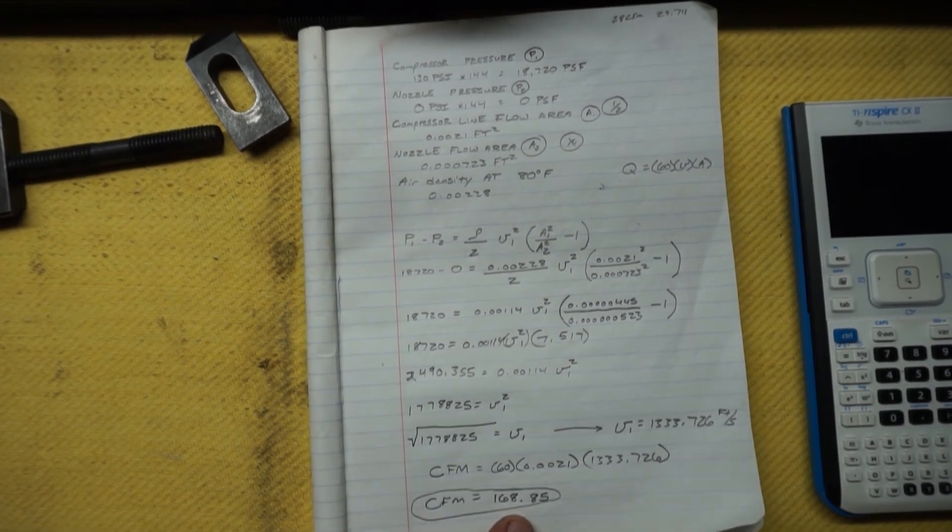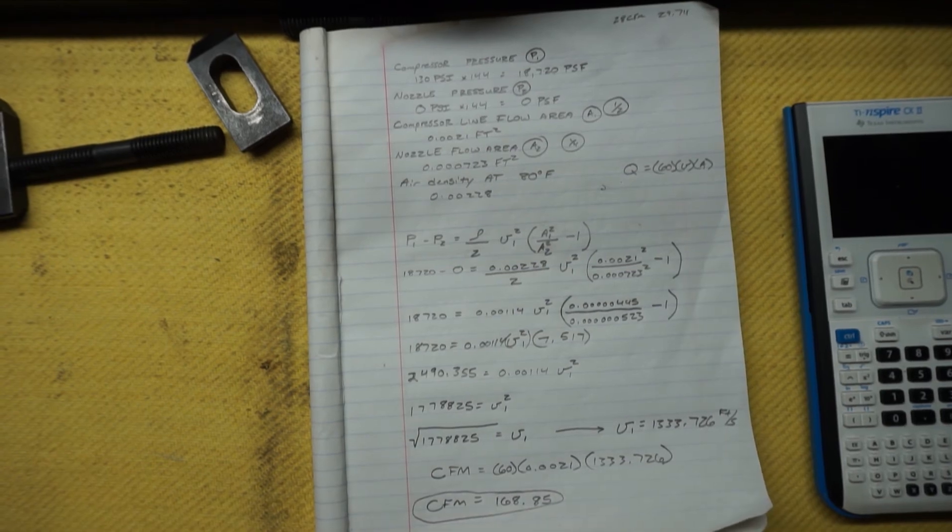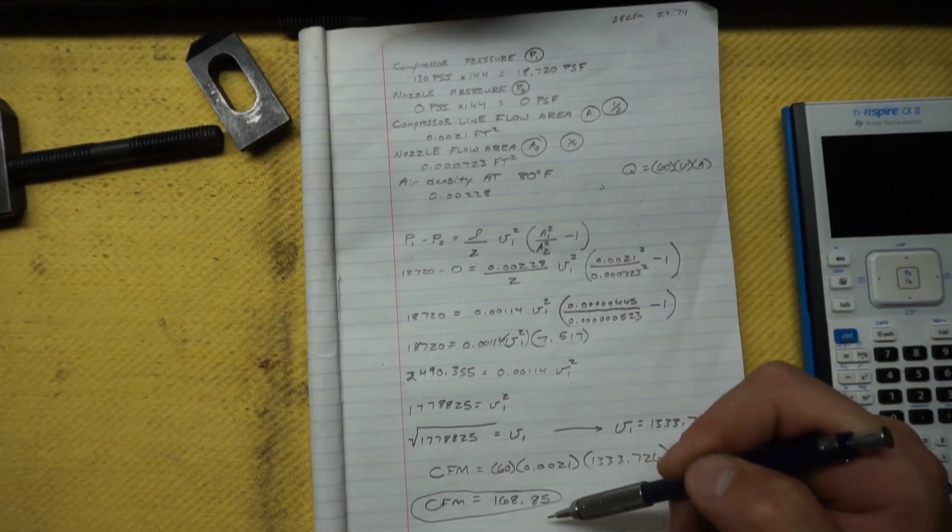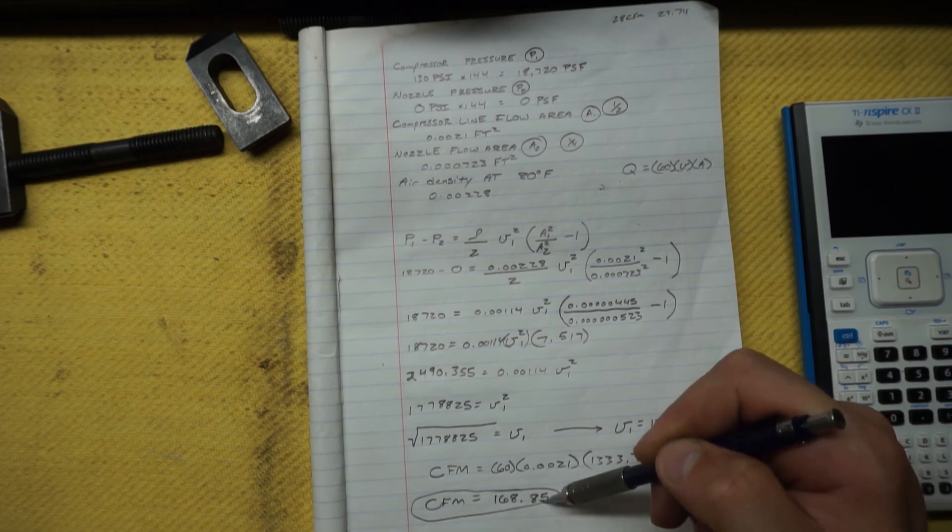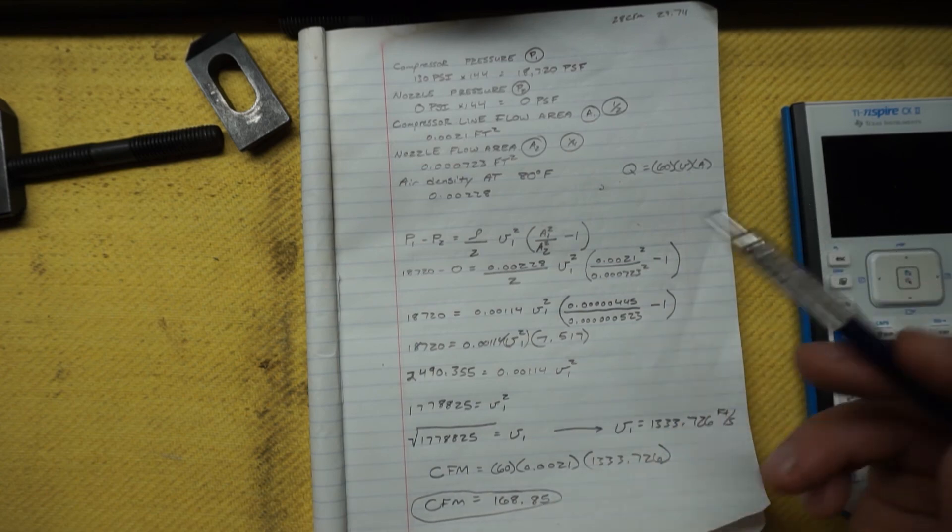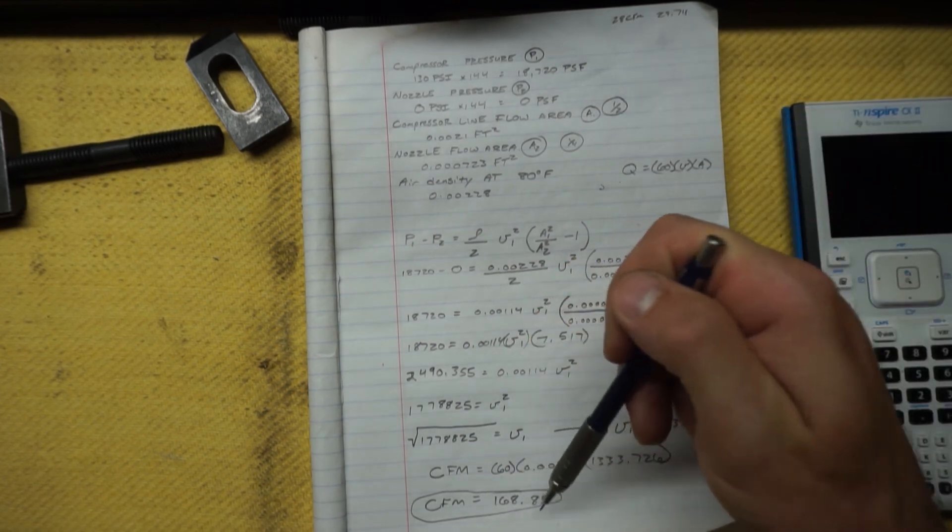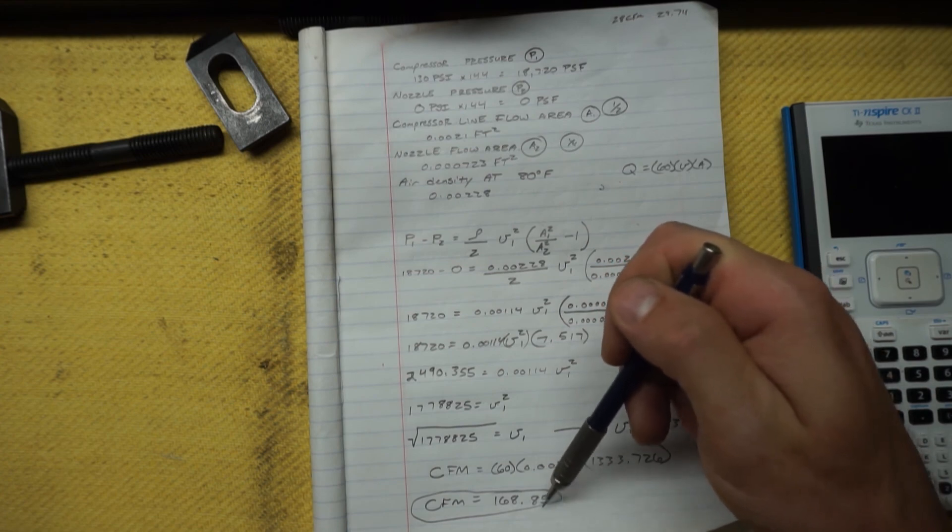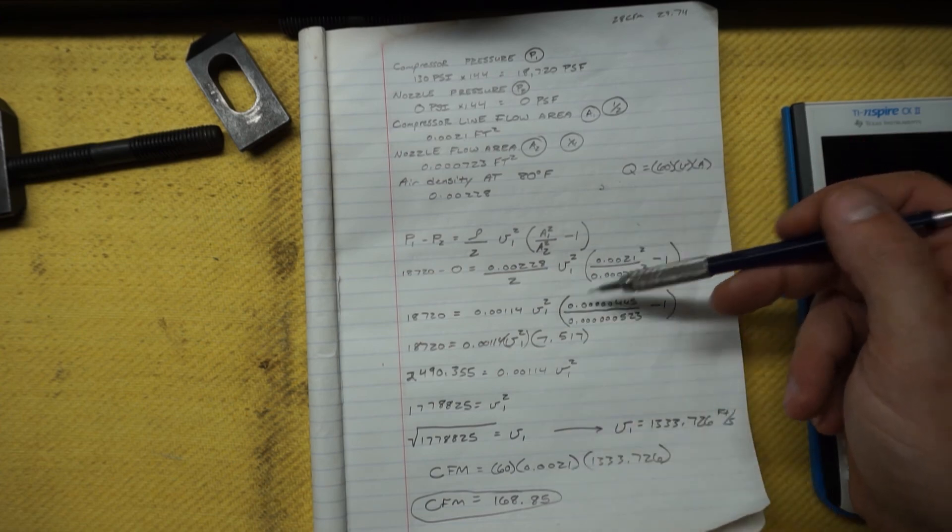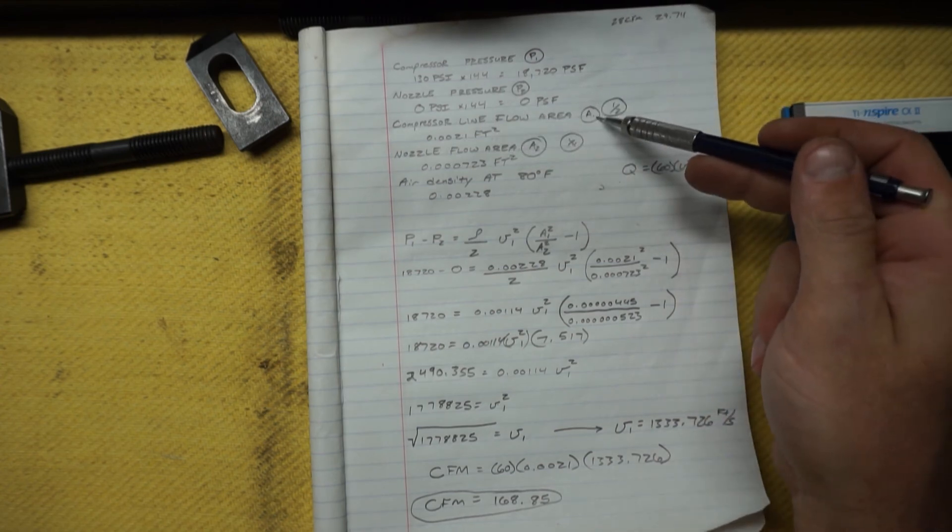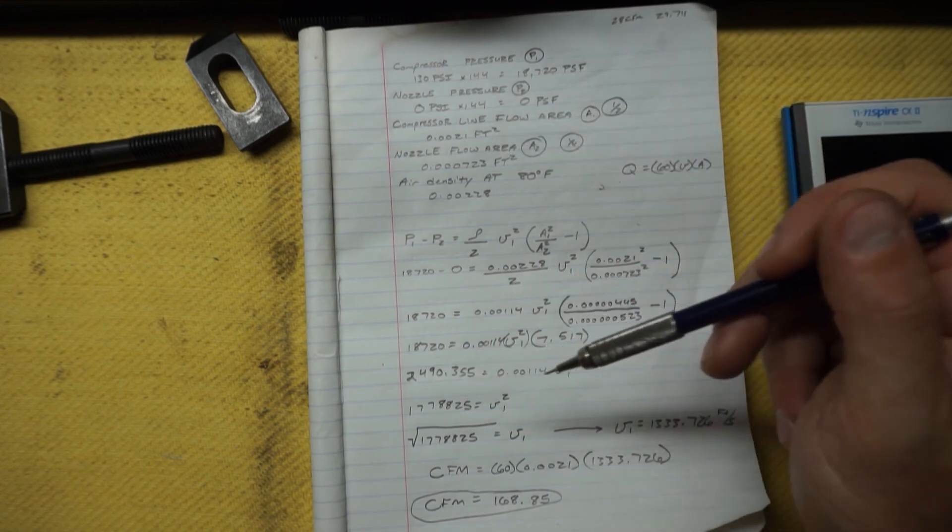Now if you have multiple items, what you would do is you would do all this math, you get the CFM. This is for the quarter inch. Now what I'll do, let's say if we have another spray gun that's another quarter inch, we don't add them together and then just say it's half inch. We do the quarter inch and then we would double this. So that would be 336 something, 337 CFM. Now if there's another one, it's an eighth inch line, you would do that inside diameter, do all this math using the same compressor A1, and then you would add it to that 337 that you just got.